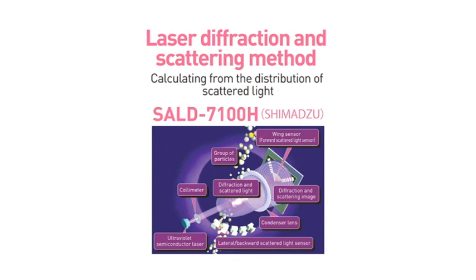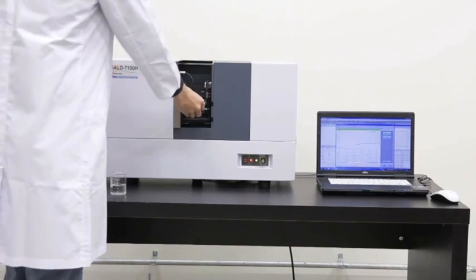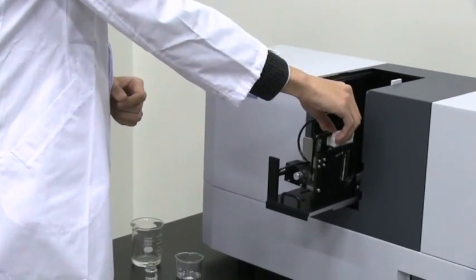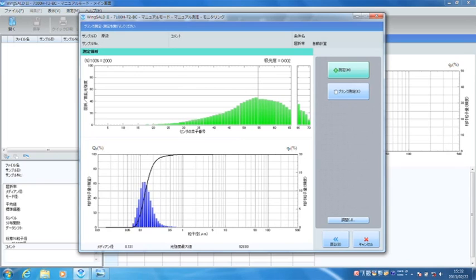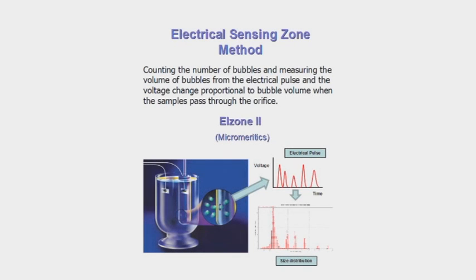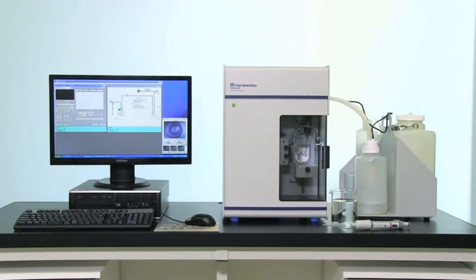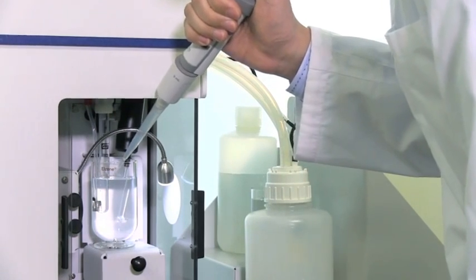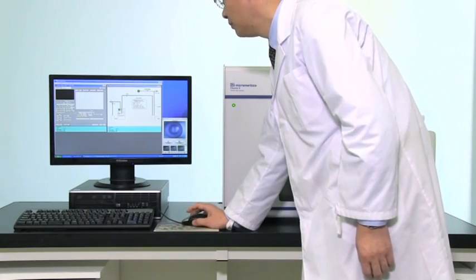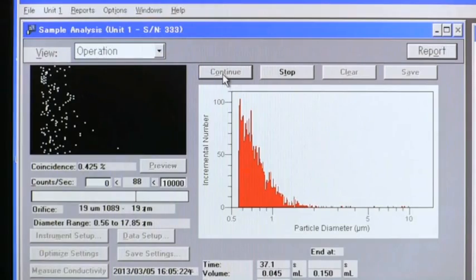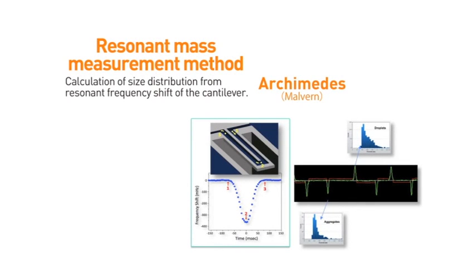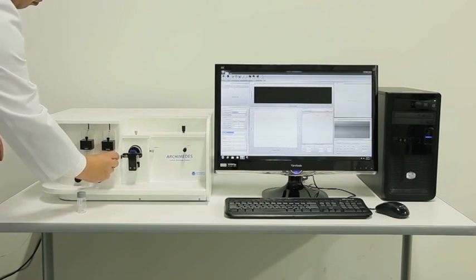A laser diffraction and scattering method that measures the angular distribution pattern of the scattered light intensity; an electrical sensing zone method that measures the volume of ultrafine bubbles and counts the bubbles; and a resonant mass measurement method that distinguishes solid particles from gas particles using a MEMS resonance device.